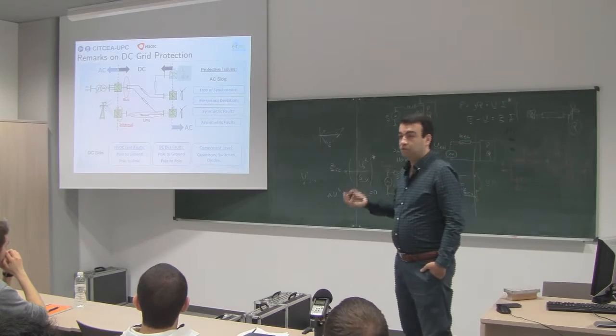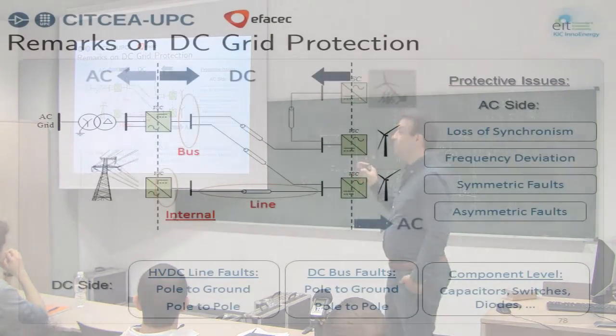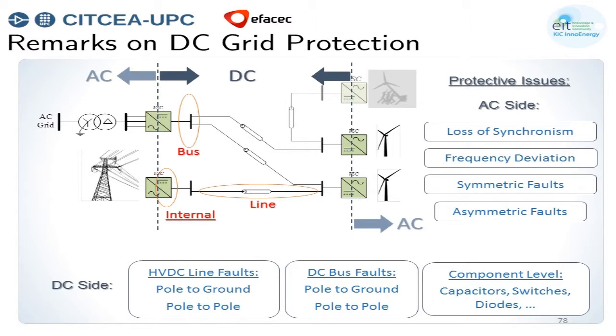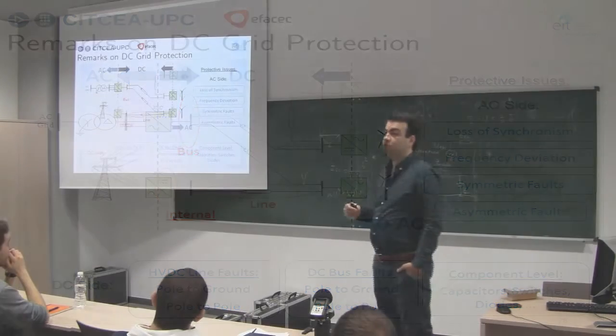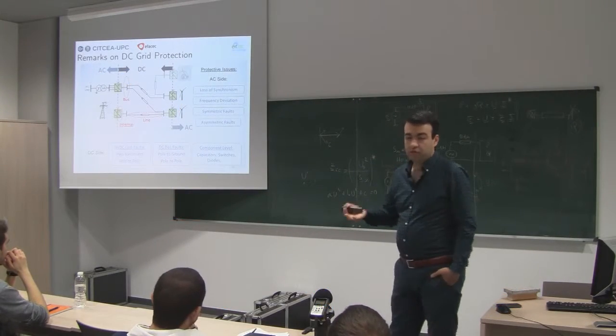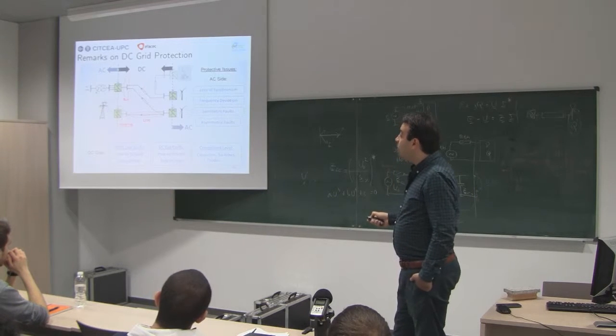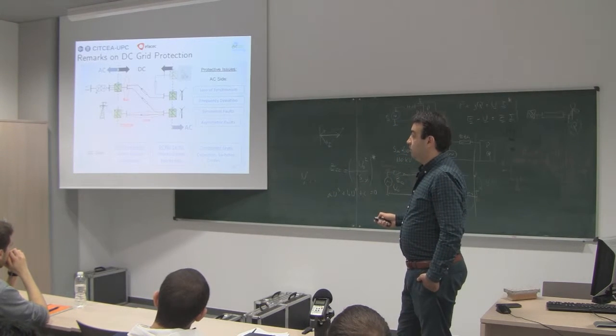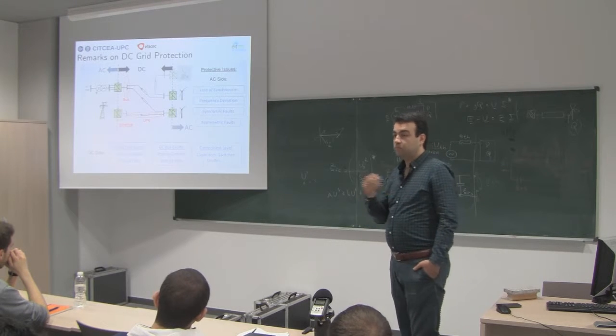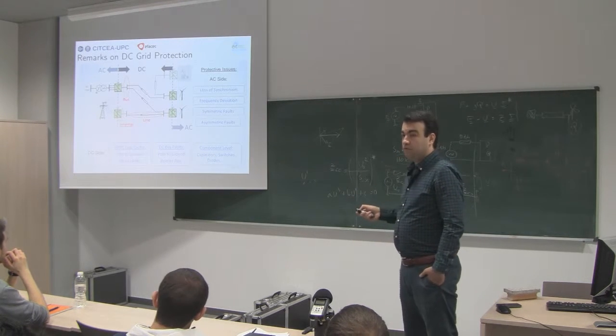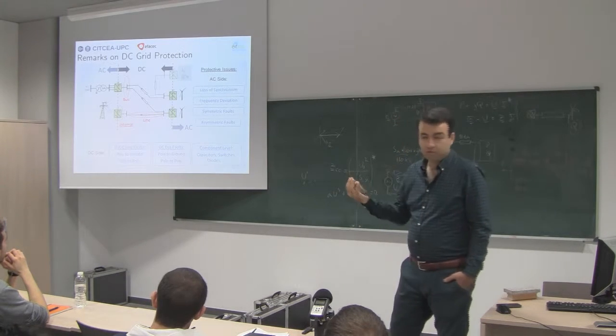We have circuit breakers in the AC system, but let's see if they will be useful for this kind of fault or not. You can see a multi-terminal grid here again. It has four terminals and one terminal is supposed to be constructed. So we have different cables. It's possible to have pole-to-pole, pole-to-ground or pole-to-pole-to-ground faults on the DC side of the grid, or short circuit faults at the DC bus, which I would say is the worst case.